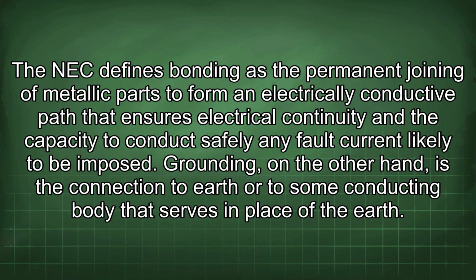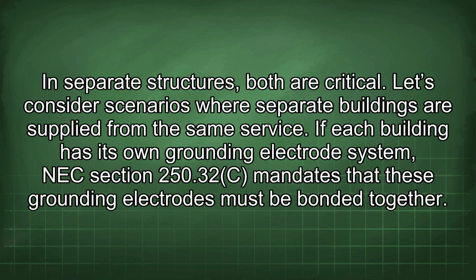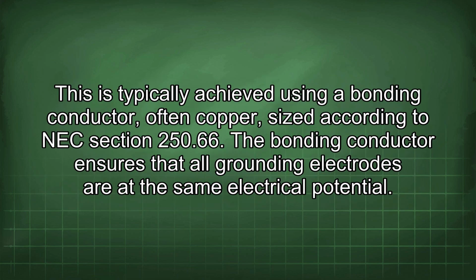Grounding, on the other hand, is the connection to earth or to some conducting body that serves in place of the earth. In separate structures, both are critical. Let's consider scenarios where separate buildings are supplied from the same service. If each building has its own grounding electrode system, NEC section 250.32(C) mandates that these grounding electrodes must be bonded together. This is typically achieved using a bonding conductor, often copper, sized according to NEC section 250.66. The bonding conductor ensures that all grounding electrodes are at the same electrical potential.